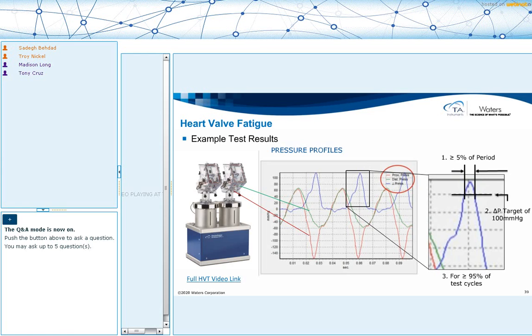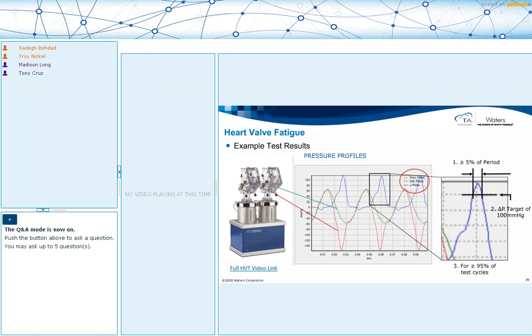So here is a zoom in of that pressure differential. The three things that we want to look at: that the delta pressure is above 100 millimeters mercury for 5% of each cycle, and the third aspect would be over several million cycles over time, that you have to make sure that for at least 95% of those, you are maintaining that pressure differential. I have a little video that I asked my colleague again to show you of how this instrument operates and how you mount your sample and all that.